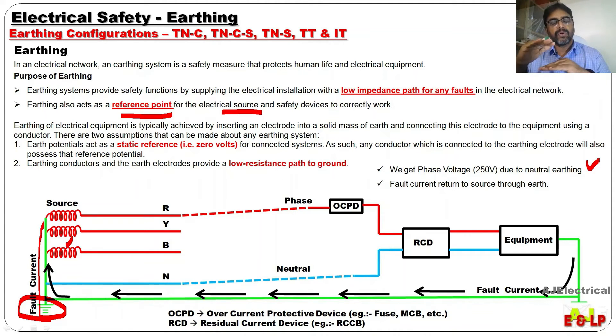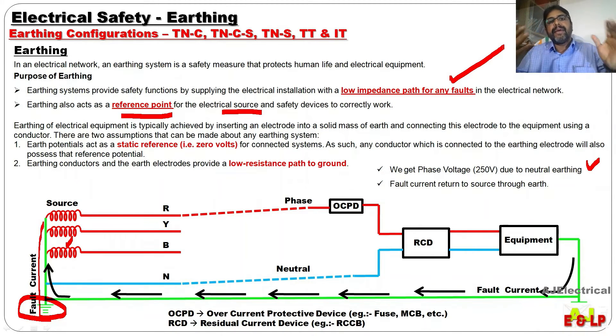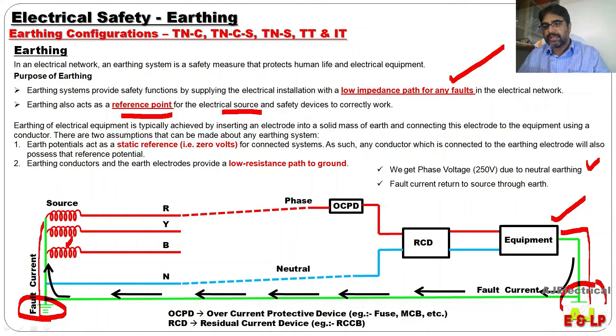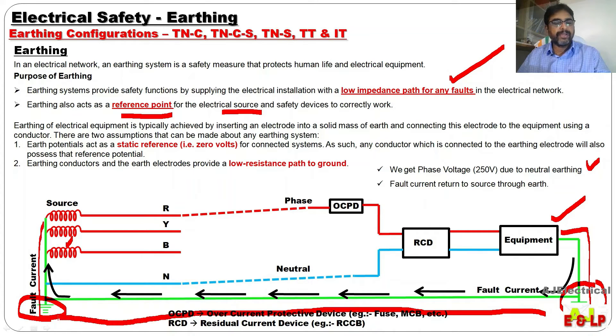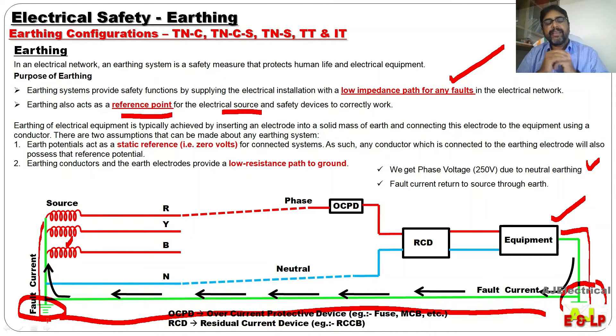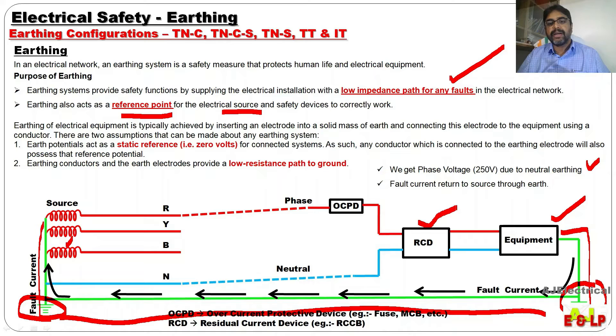So the purpose of earthing is to get a constant single phase voltage. The other purpose is to make a low impedance path for any fault. Suppose consider an equipment — it is having a metal enclosure. That must be earthed. By earthing, that what will happen — through this earthing it is getting into contact with the neutral of the source. So if there is a fault, that fault current will run to the source. So by neutral earthing we are creating a path for the flow of fault current. When it is passing to the source, the overcurrent protection — or the residual current device, if it is RCD or RCCB — will work depending on the fault current.